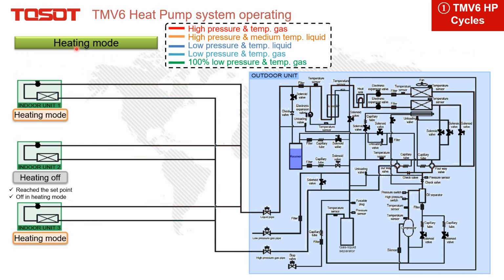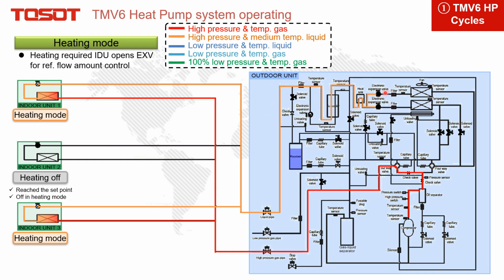This slide is the heating mode in the heat pump system. I also put indoor units 1 and 3 in heating mode, and indoor unit 2 is heating off, which means it reached the set point or remains off. How the refrigerant flows: from the compressor, the refrigerant will first flow to the indoor unit, as there are no valves to stop it. So it gets into the indoor heat exchanger to make heat exchange. Then it becomes liquid, gets through the EXVs, goes back to the outdoor unit, and then to here.